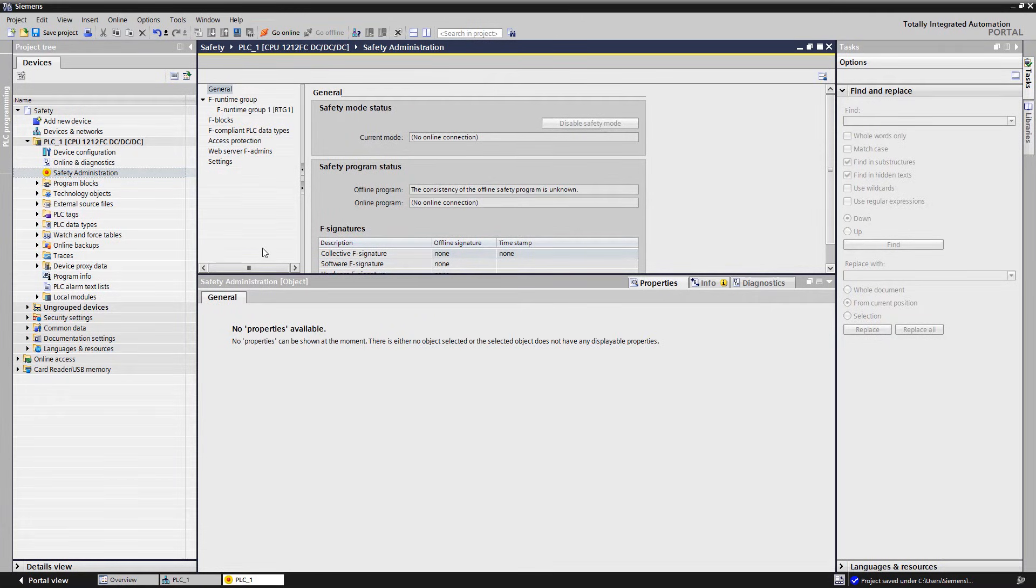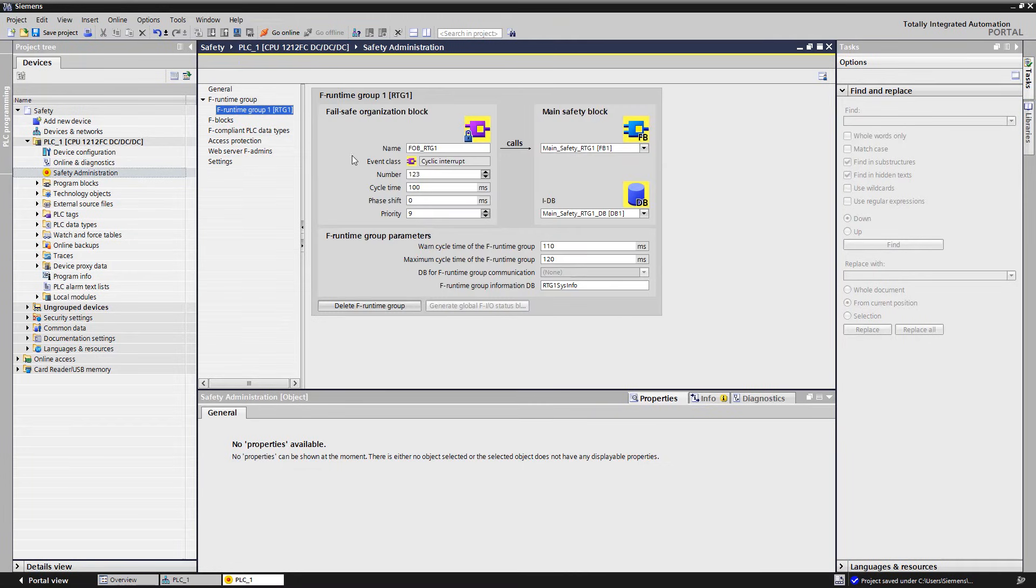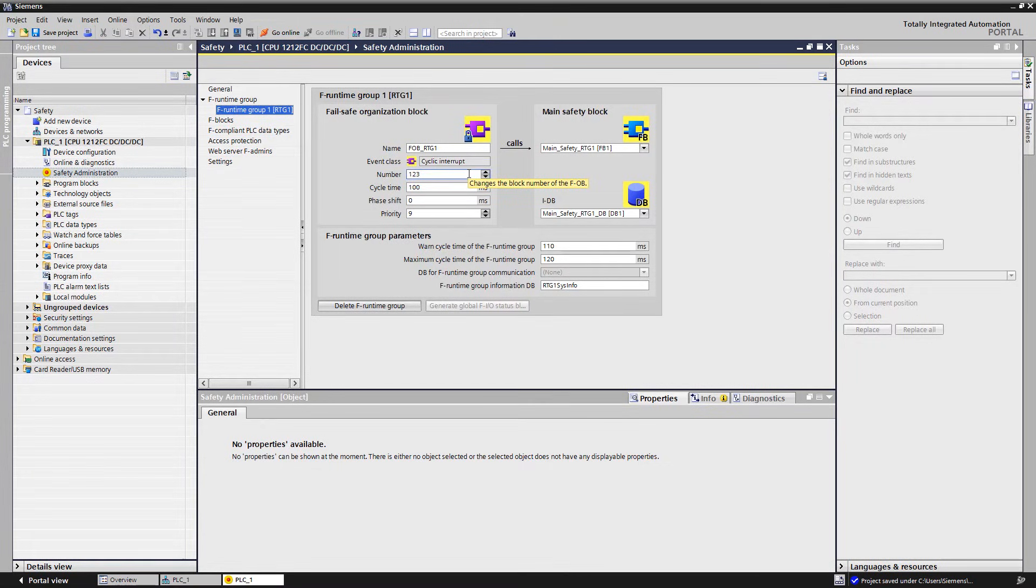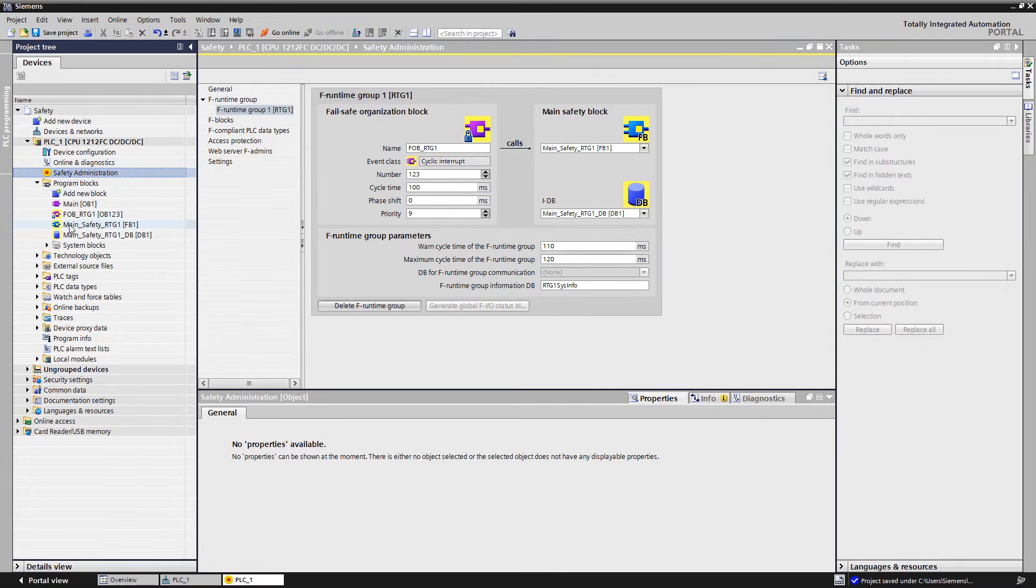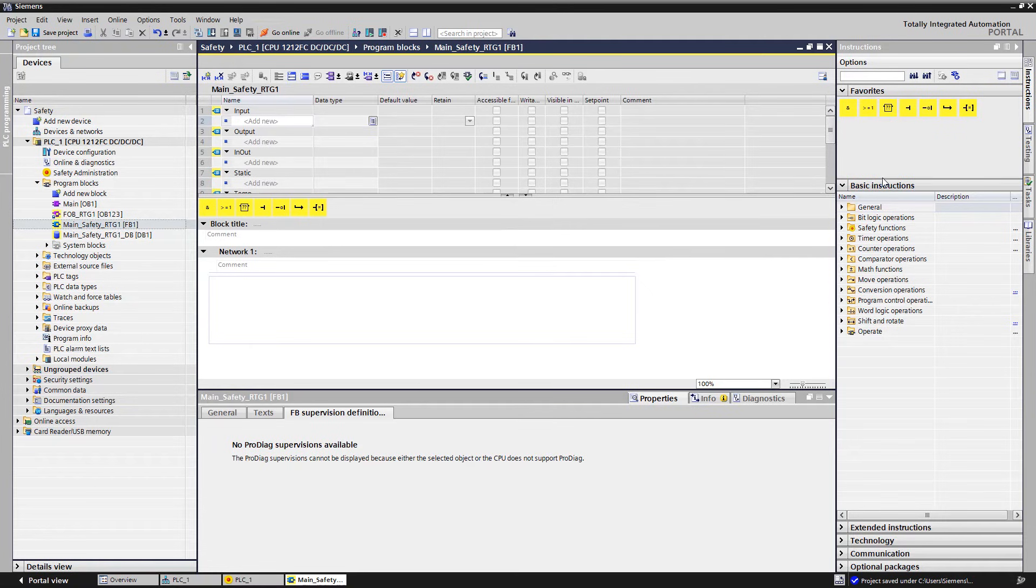The OB123 calls the main safety FB, which includes our safety program. Here we see the setting of the cycle time, which shows how often the F program is called, the priority, as well as a warning limit for the cycle time and the maximum cycle time that must not be exceeded. We directly start in the main safety module of our F runtime group.